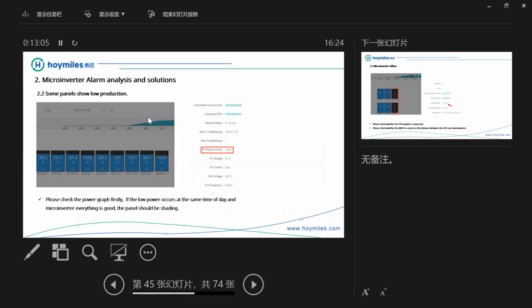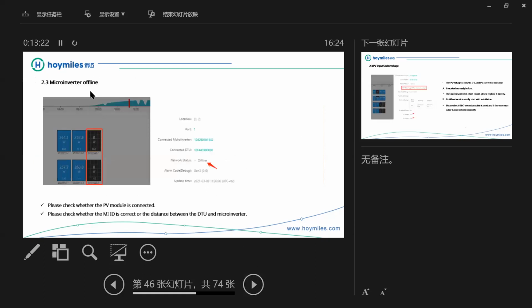If some panels show low production on the monitoring platform, please check the power graph first. If the low power occurs at the same time of day and the microinverters are all good, the panel should be shaded or affected by other environmental factors. If the microinverter shows offline, please check whether the PV module is connected, whether the MI ID is correct, and whether the distance between the DTU and the microinverter is too far.